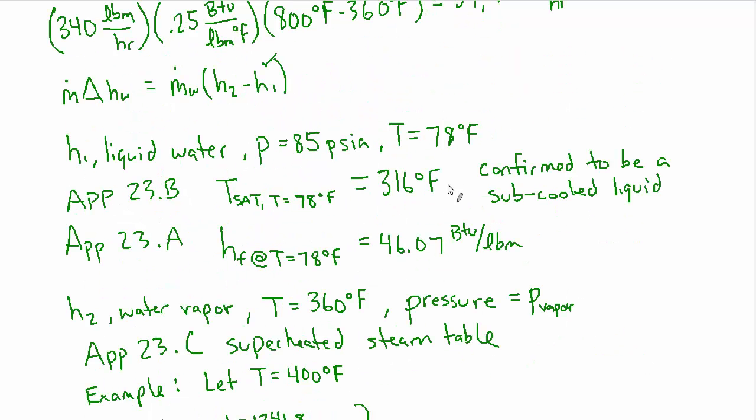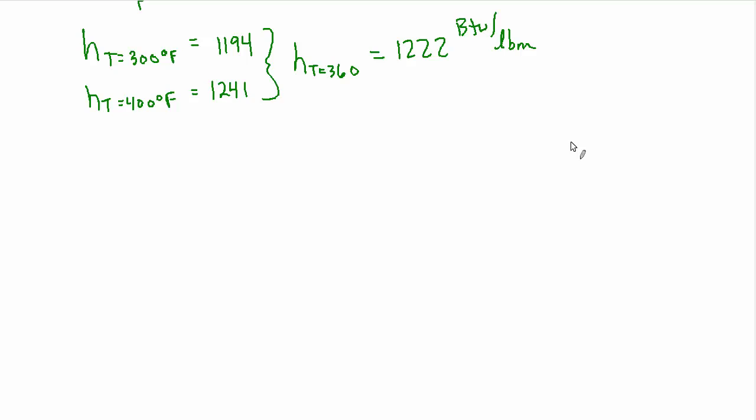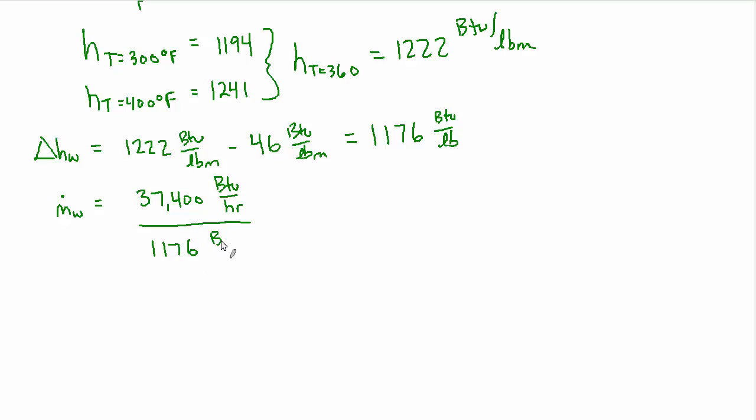Okay, so now we can come back up to our main equation here, M delta H, which we were going to set equal to 37,400. So let's pick it up with delta H. We now know delta H for water equals that 1222 that we just found minus the 46 from the liquid water, which is about 1176 BTU per pound. And now we can solve for the mass flow rate of water, which is the total energy from the left side of the equation, which we had as 37,400 BTU per hour divided by our delta H 1176 BTU per pound mass, which gives us a mass flow rate for the water of 31.8 pounds per hour. And that is answer A.